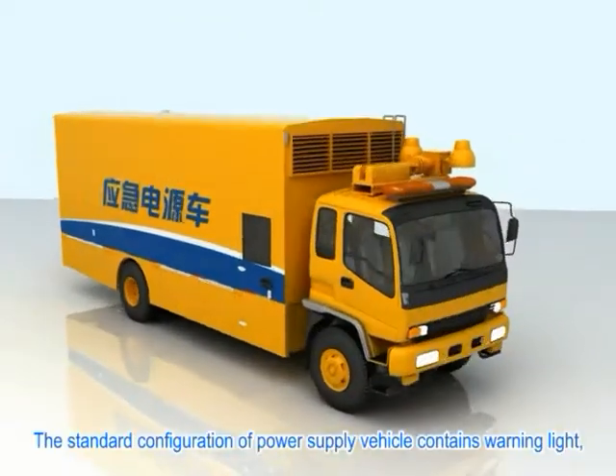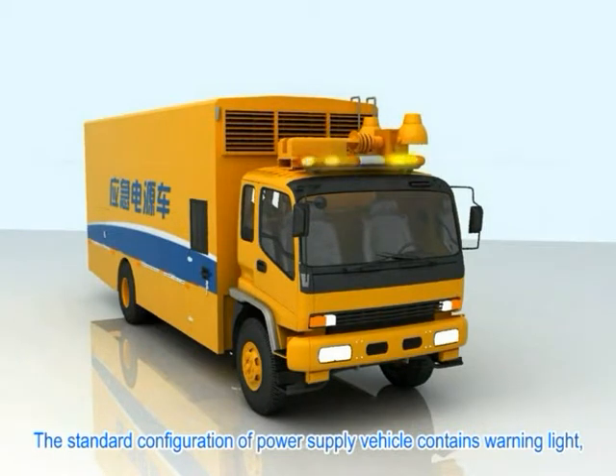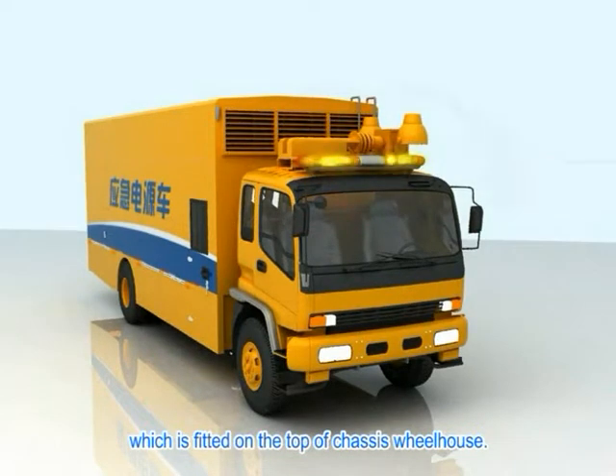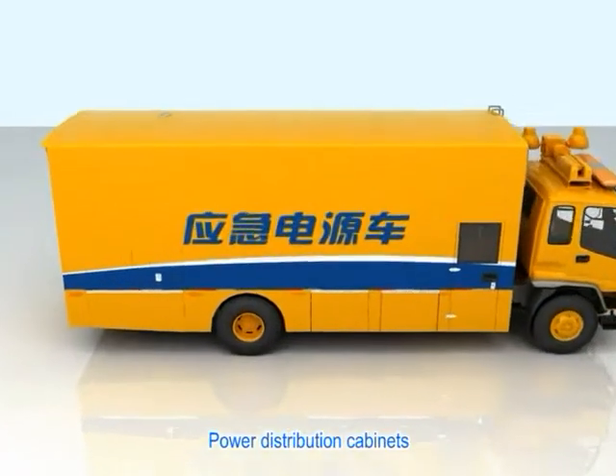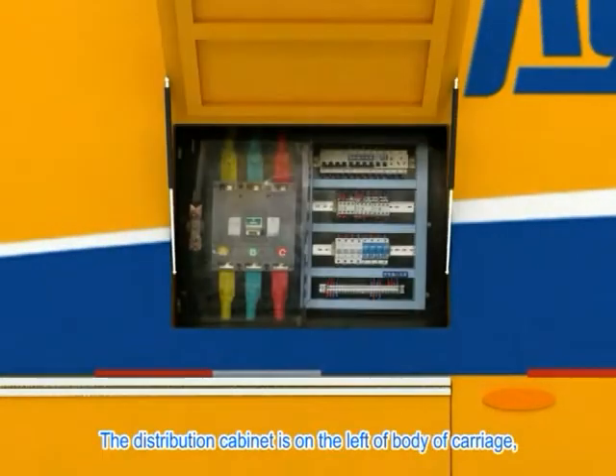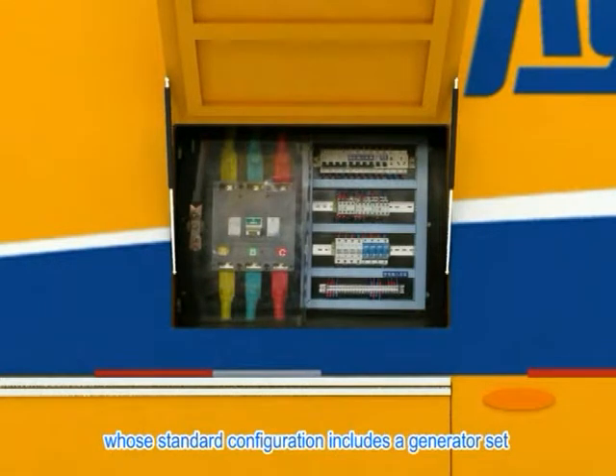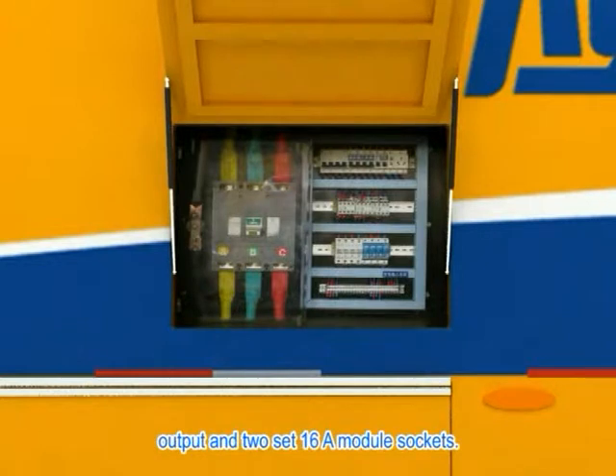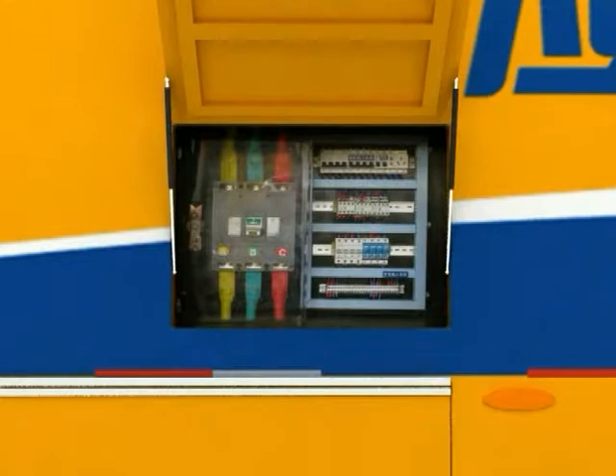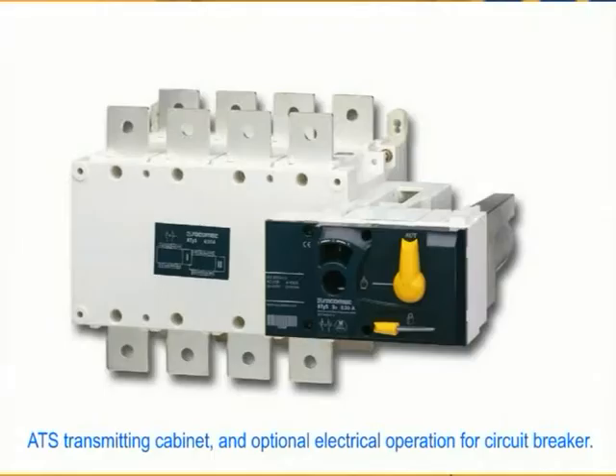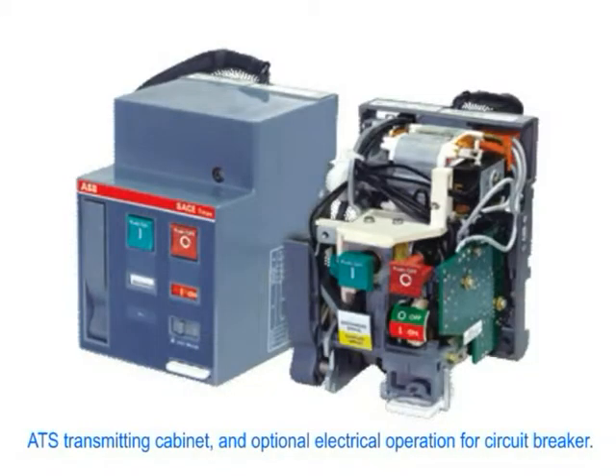Warning light. The standard configuration of the power supply vehicle contains a warning light, which is fitted on the top of the chassis wheelhouse. Power distribution cabinets. The distribution cabinet is on the left of the body of the carriage, whose standard configuration includes a generator set output and two sets of 16 amperes module sockets. According to user requirements, we can install multi-loop outputs, an ATS transfer cabinet, and optional electrical operation for the circuit breaker.